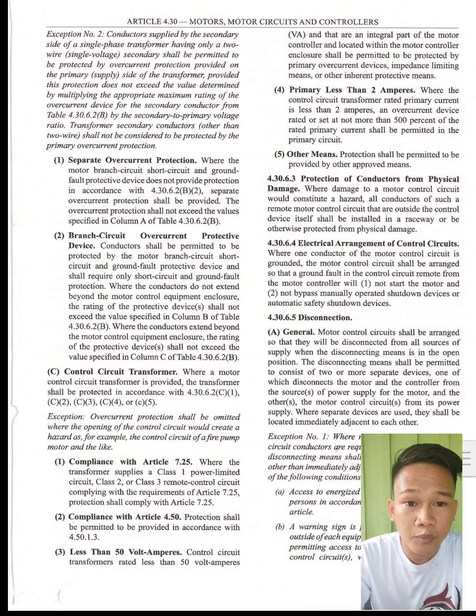Next, we have 4.30.6.3. Protection of conductors from physical damage. Where damage to a motor control circuit would constitute a hazard, all conductors of such a remote control circuit that are outside the control device itself shall be installed in a raceway or be otherwise protected from physical damage.